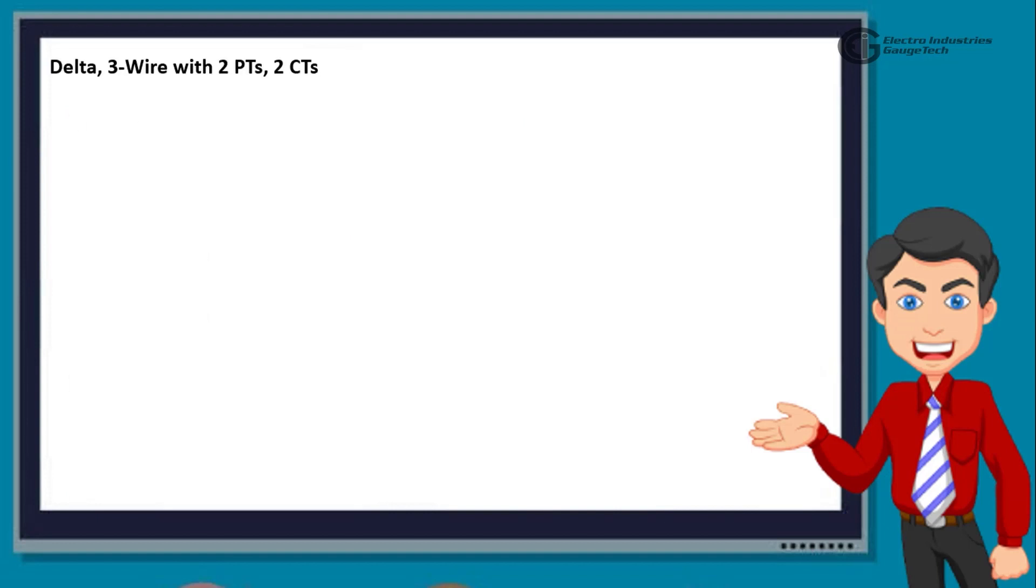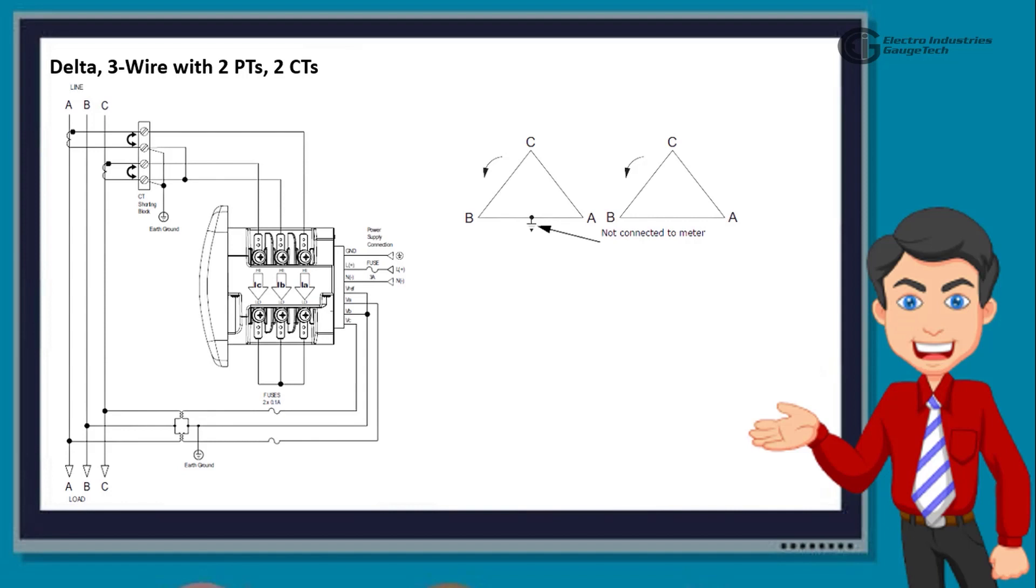Now, we have Delta, 3 wire with 2 PTs, 2 CTs. In this diagram, you will see the 3 phase, 3 wire Delta system with 2 potential and 2 current transformers. When using this wiring, select 2 CT-Delta from the Shark Meter's front panel display.